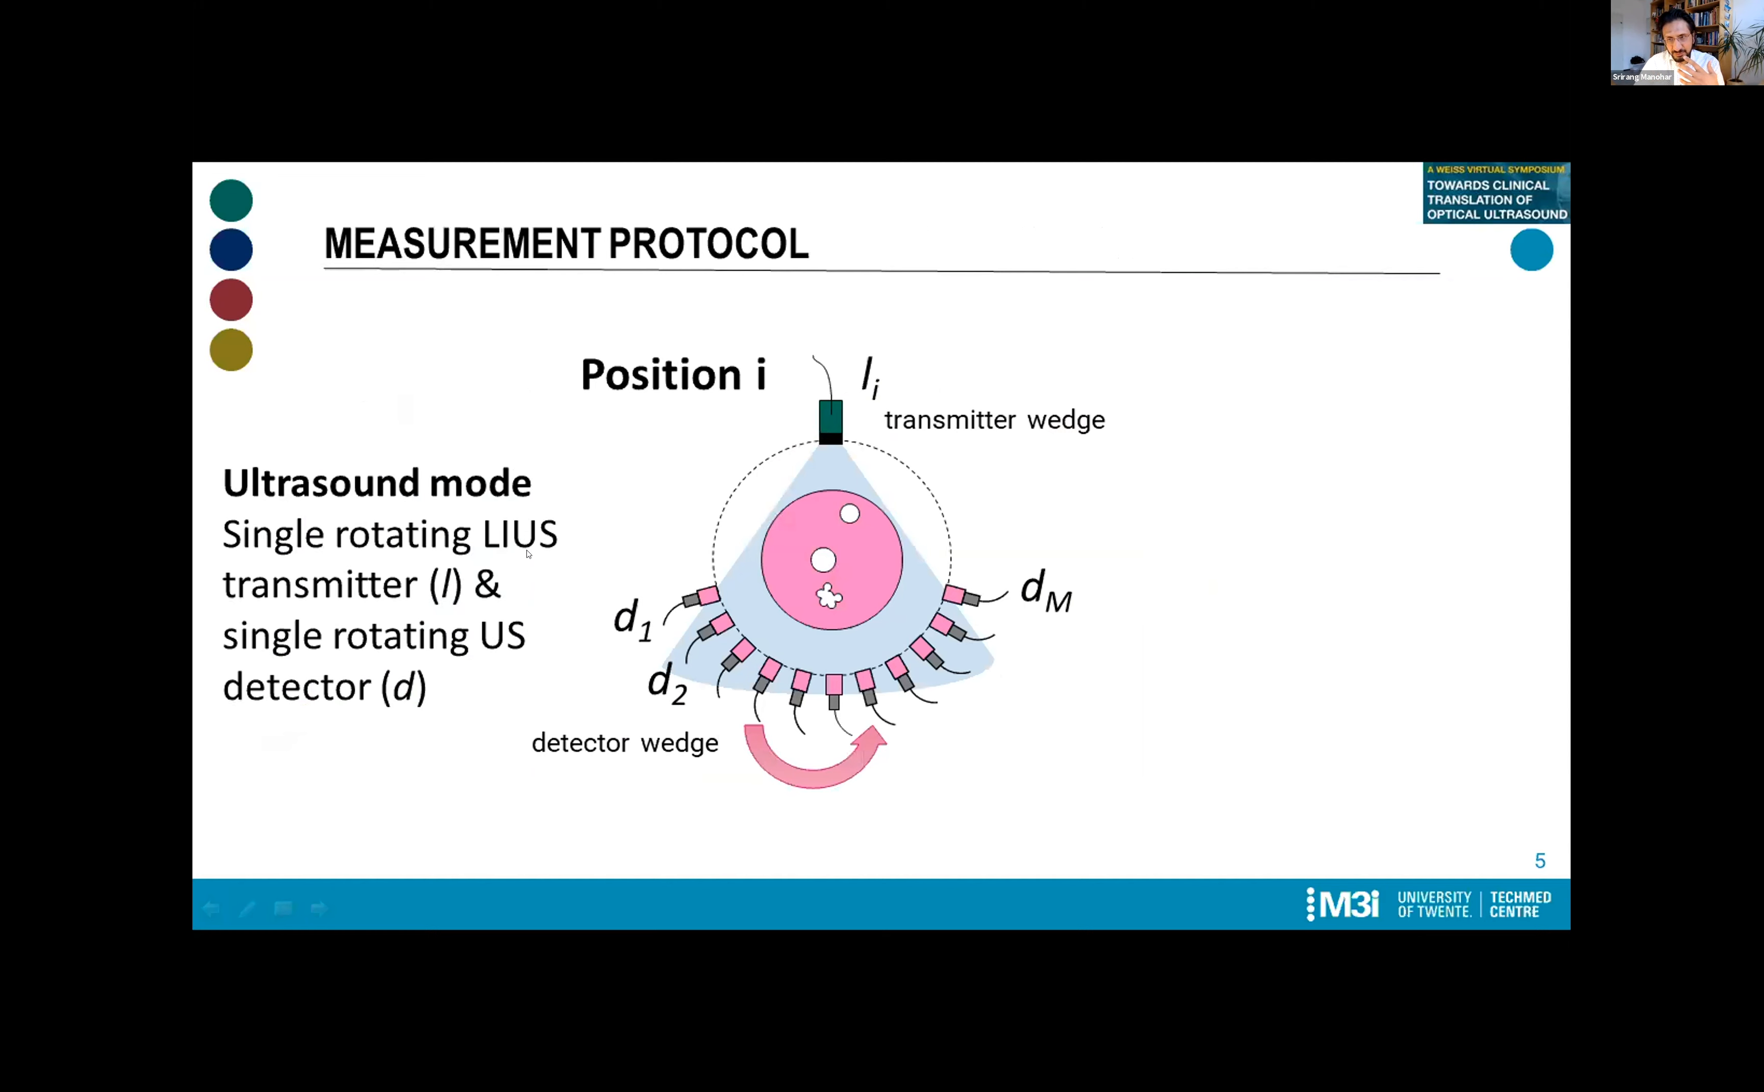In the ultrasound mode, you can also do photoacoustics, but in the ultrasound mode, we have the transmitter occupying a stationary position for the first set of acquisitions, and we move the detector wedge so that the detector is sampling the cone beam of the insonifying field. This is only in 2D, I should say, and then we go to a second position of the transmitter and replicate this acquisition.